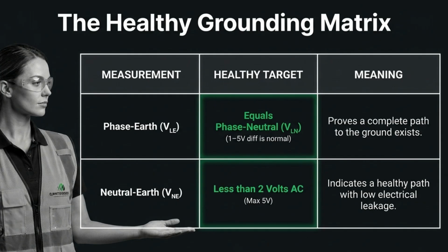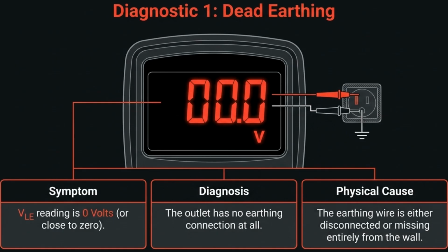A phase earth reading equaling phase neutral proves a complete ground path. A neutral earth reading less than 2 volts AC indicates low electrical leakage. Diagnostic 1. Dead earthing. The symptom is a VLE reading of 0 volts, or close to 0, meaning the outlet has no earthing connection. The physical cause is a disconnected or missing earthing wire.